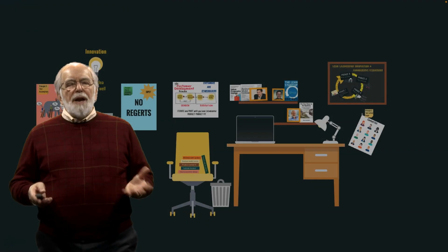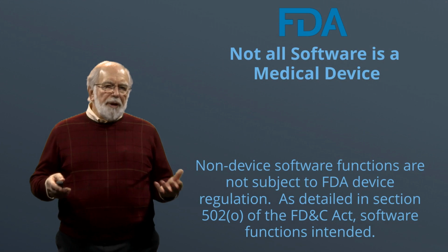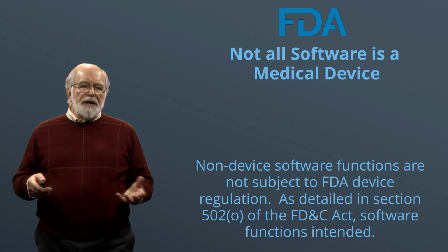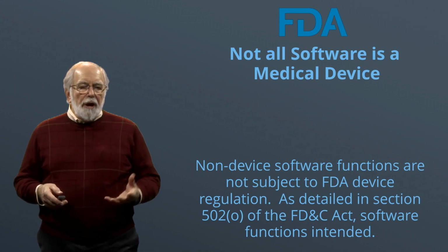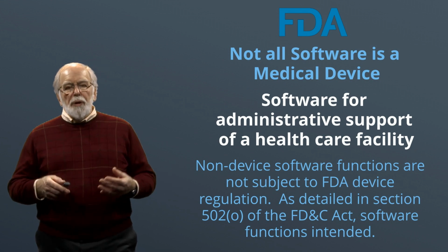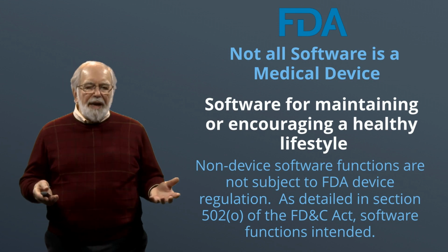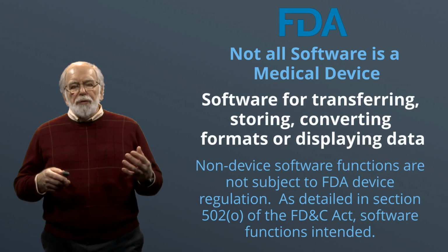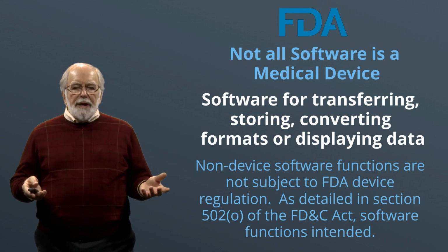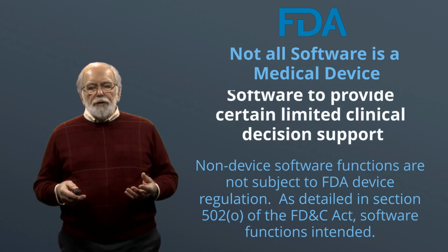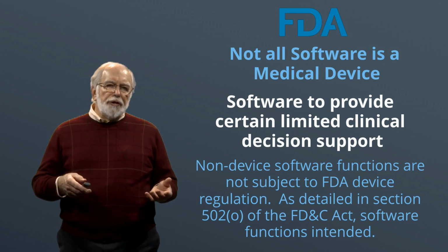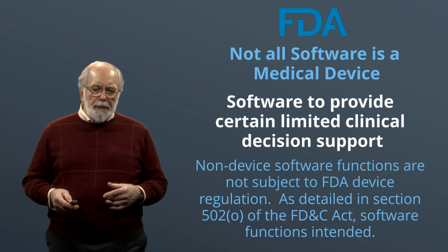You should be aware that not all software is considered a medical device. Some examples in the healthcare system that are not considered as medical devices are administrative support to a healthcare facility, software that supports that, or software for maintaining and encouraging healthy lifestyle, or software for transferring, storing, converting formats is also not regulated by the FDA. And also data software that provides for certain limited clinical decision support is also not regulated by the FDA.